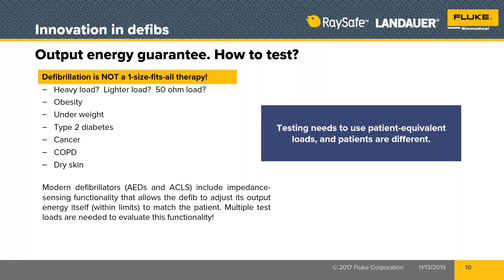But in order to test whether that functionality is working properly, you have to have more than just the standard 50 ohm test load that has been required in and built into defibrillator analyzers for many, many years. So what do you do about that? Well, we need to have some ability to provide additional resistance values or load values above and below that 50 ohms, because the average impedance of the patients across the world today is really more like 70 ohms, not 50. So we just need to be able to do that. You can't test these functionalities with just that one single 50 ohm load. So what do we do?